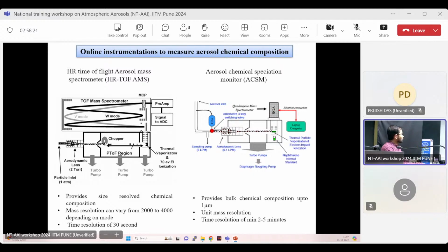In this detection there are two types: one is quadrupole detection, and the second is the time of flight detection that we are using here. In quadrupole detection, we select voltages, and those voltages correspond to the different masses. In SMPS, Mariam already mentioned that you have to select some voltages in order to get different sizes, which you will see in the SMPS demonstration as well. A similar analogy applies, but not for particles, for masses.